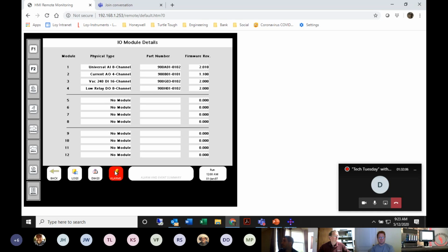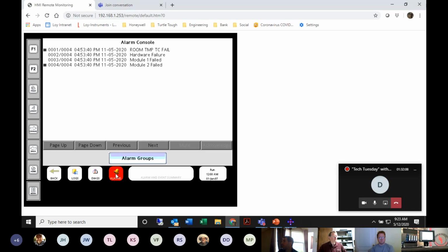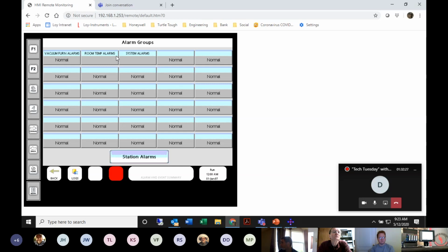The other screen here, which is the alarms, I'm going to click on that right now. This is another pre-formatted screen. What it'll tell you is when a certain point went into an alarm. It'll have the tag of that point, so it'll tell you exactly what it is. And I can click on alarm group, and now I can actually group alarms and acknowledge those based on the grouping.